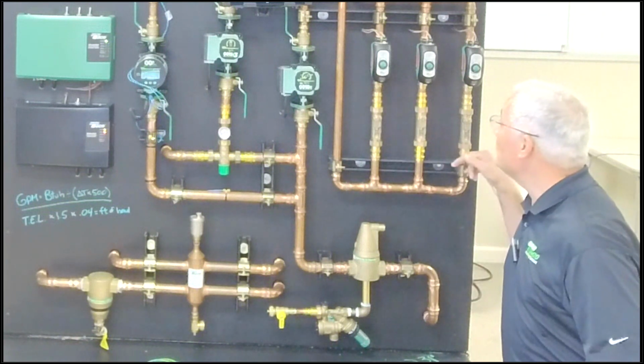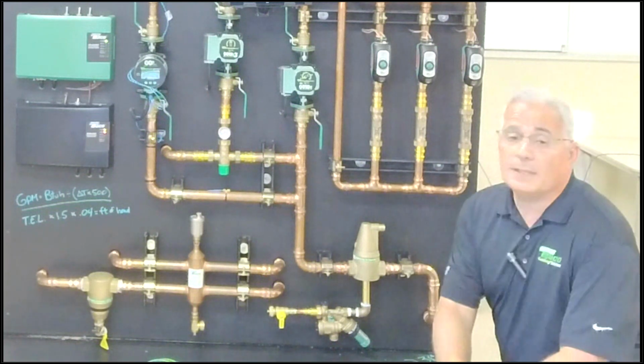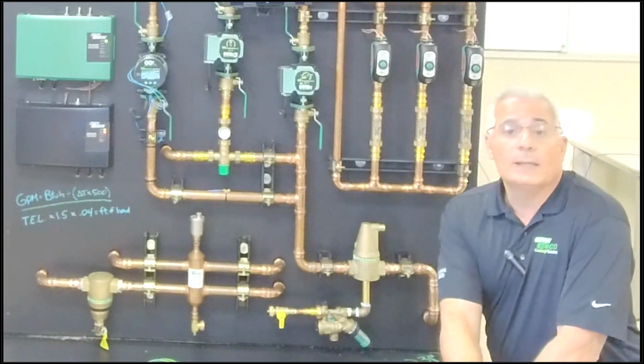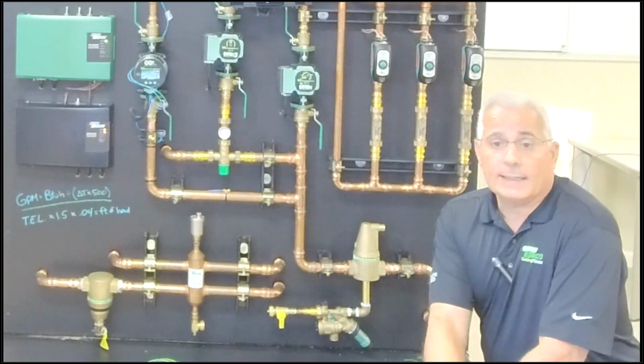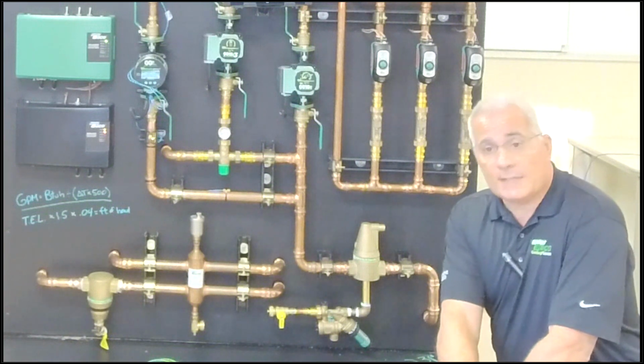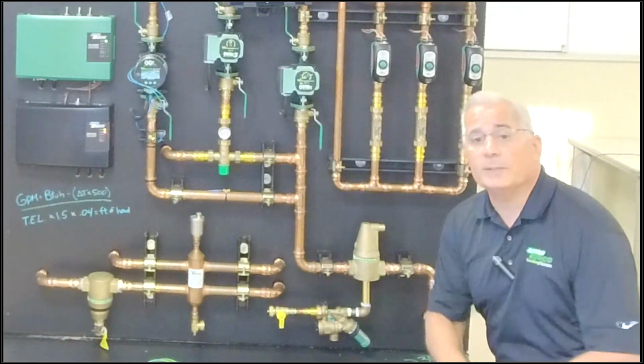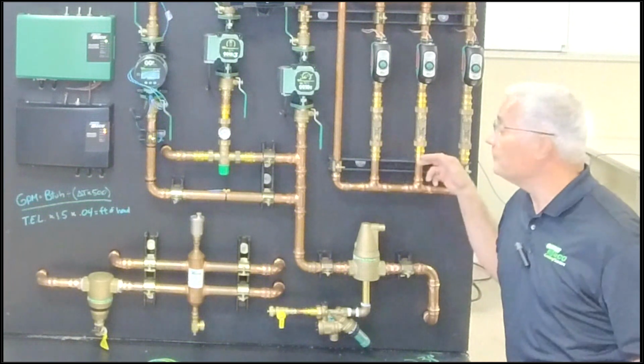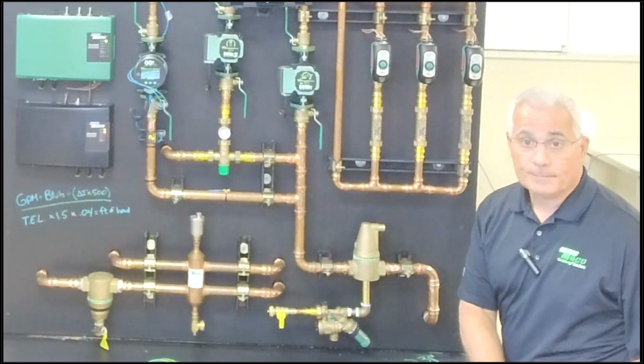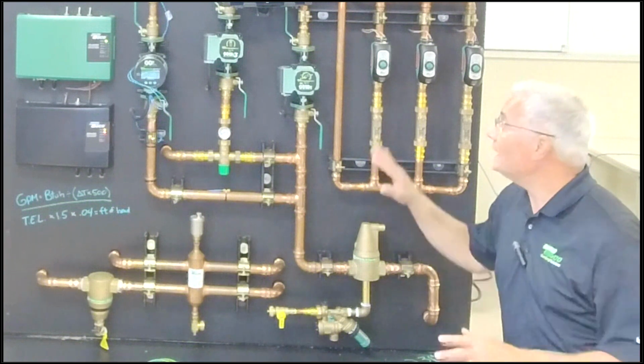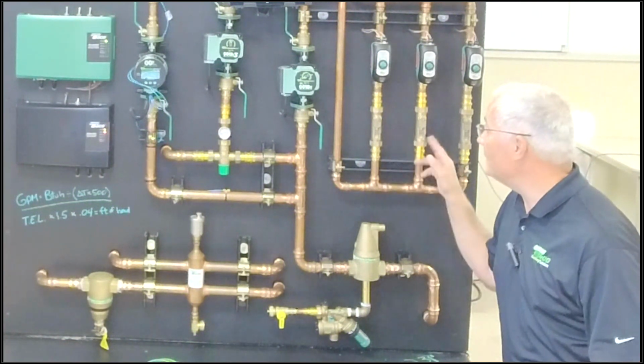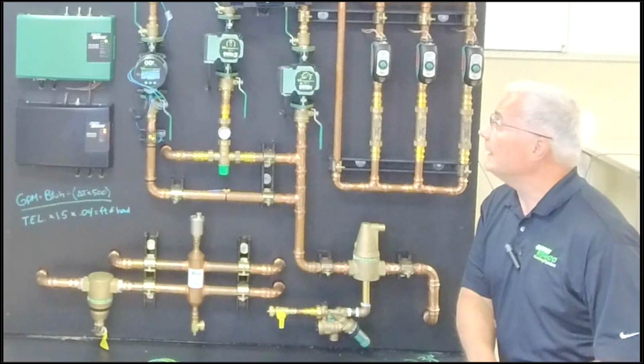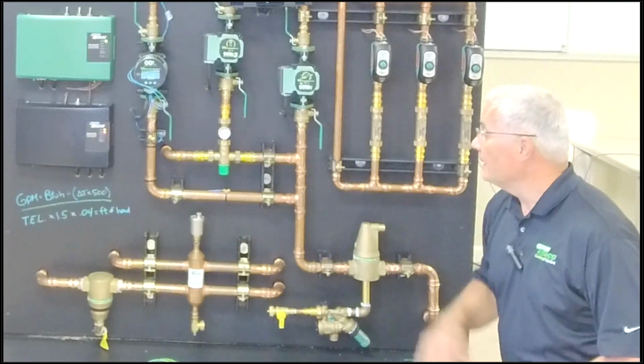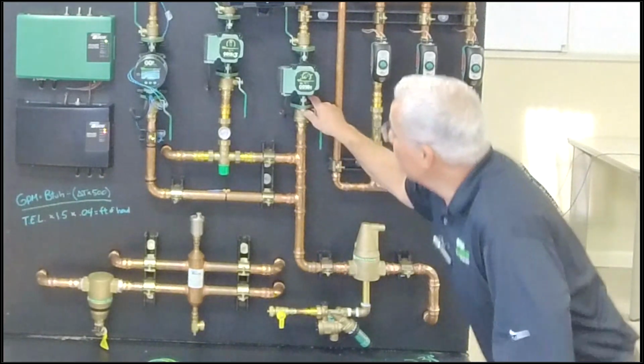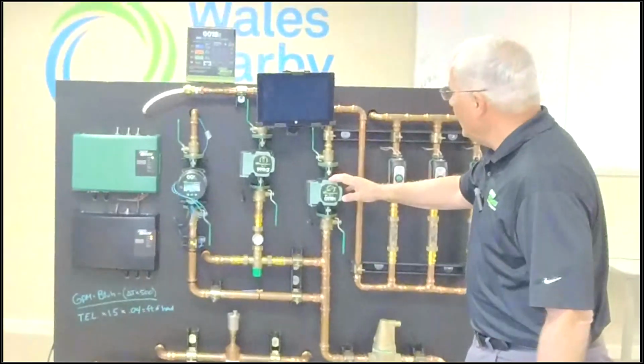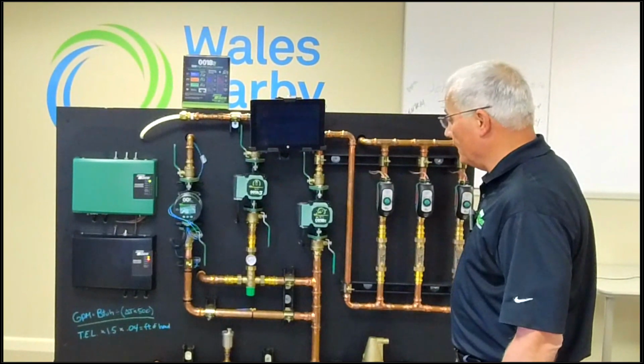We are using 3/4 piping here going out to our zones. The potential through that piping, if you do recall, was 4 GPM, again making sure we're not going over 4 feet per second. Using the universal hydronics formula in reverse, that would be the potential of 40,000 BTUs at each loop. We do not have 40,000 on this job because I can measure the GPM here, and we'll show you that as we're running the system. So I'm pumping away, I'm pulling through. This is my system circulator, and I'm going to my individual zone valves.